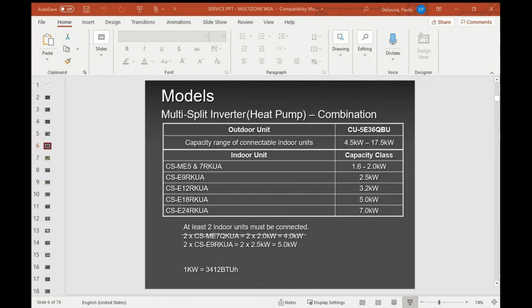Yes. Okay. So guys, I hope everything is okay on your end. I'm going to explain to you. I am in presentation mode, but for some reason it's not getting converted on your end. But anyway, as I mentioned to you, our multi-zone minimum is 2 indoor units. However, you must obey and respect the minimum and maximum capacity. Now, in this case, the guy picked two 7,000s. Two 7,000s bring only 4 kilowatts, which is not enough. So when they turn it on, you will have a problem. It says capacity error, which is error code H12. We'll talk about it later.